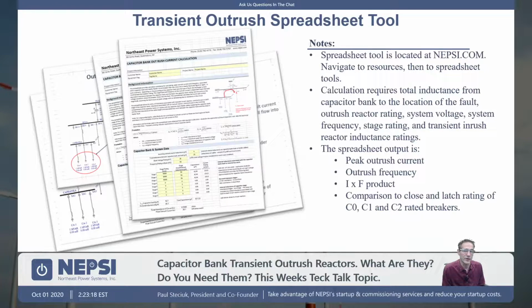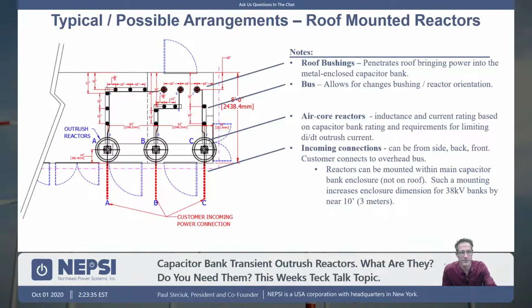We have one for transient inrush, and we have one for transient outrush. And so you can actually view both calculation procedures. The calculation procedure is essentially the same, but the setup of the spreadsheet is slightly different. When you look at the typical or possible arrangements, we oftentimes will put our outrush reactors on the roof of the enclosure. The reason being is because they're really large. They're large reactors, large air core reactors.